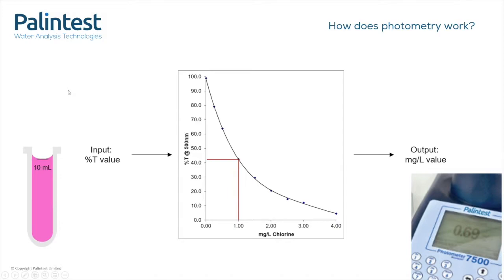So, here is a typical calibration curve. This one here is for free chlorine testing using DPD. The percent T value is converted to a milligrams per litre concentration using the calibration curve, and this readout is displayed on the instrument. In the example here, 43% T is equivalent to one milligram per litre of free chlorine. This calibration is determined in our labs and is stored on the instrument memory, so all the user will see is the displayed reading. All the calculation happens behind the scenes.